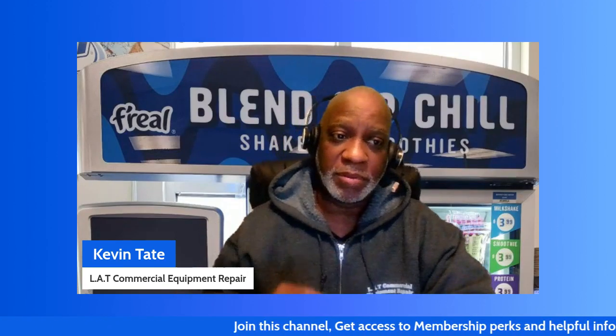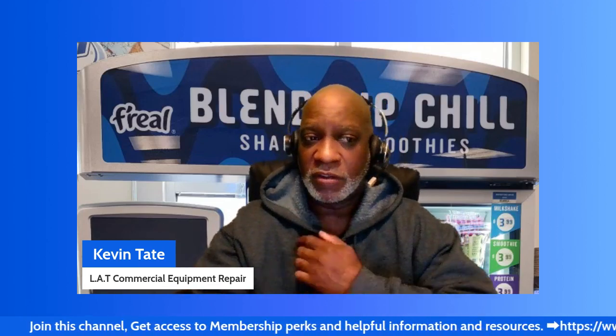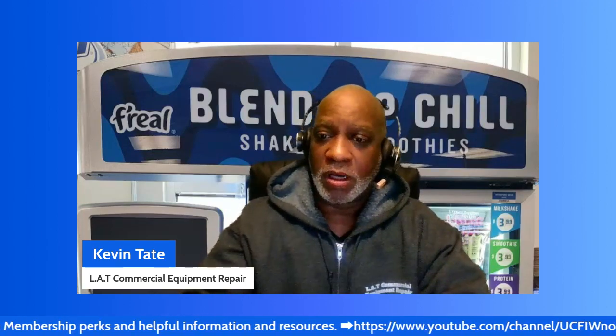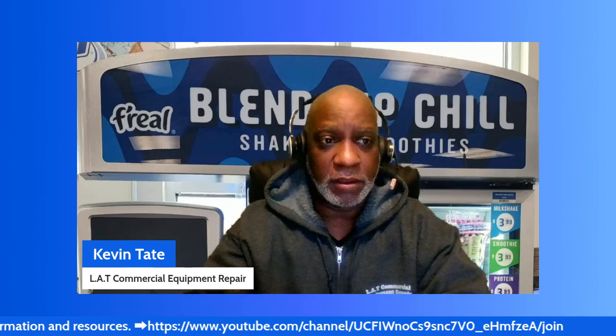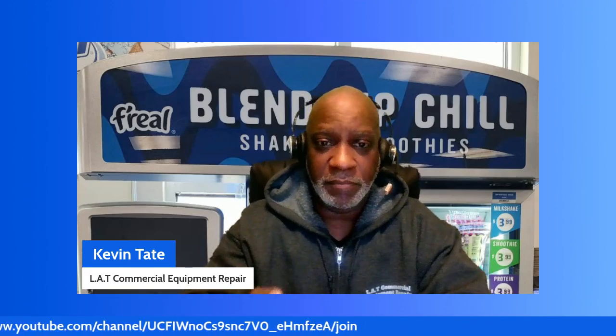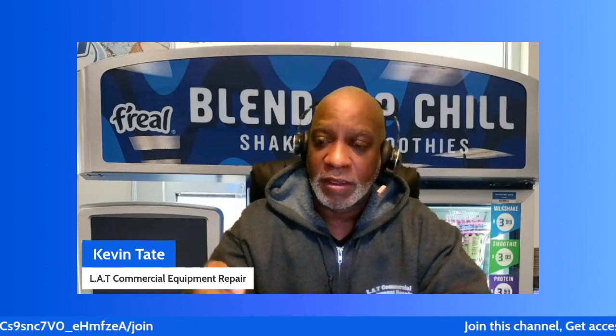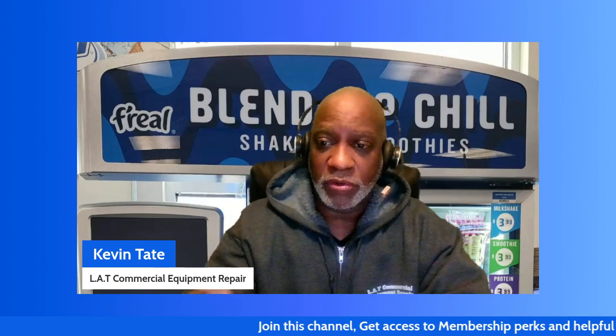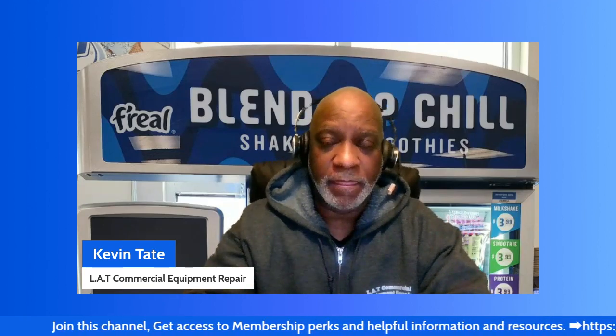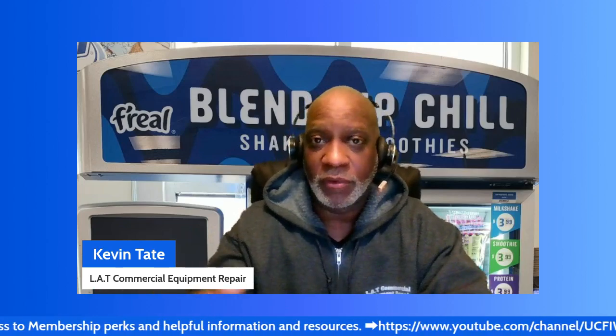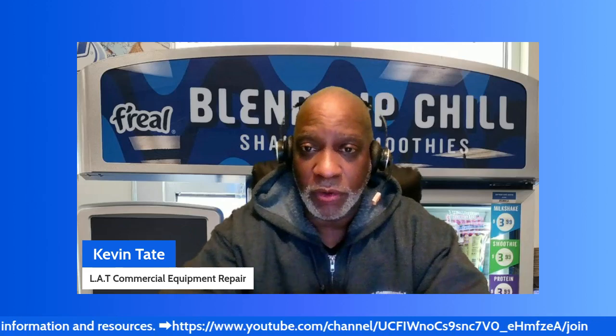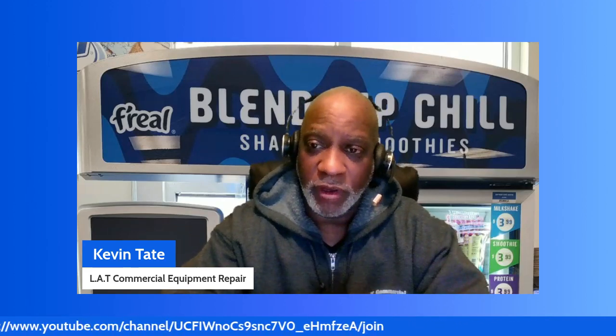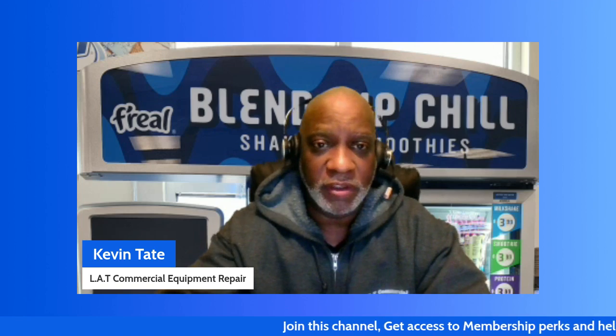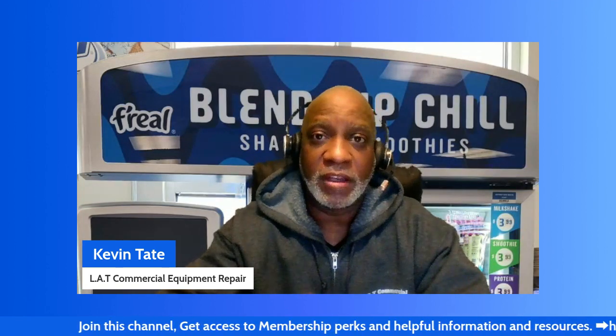You'll want to order that board and the motor and replace those at the same time. Don't take a guess and replace the HVCB board first, then test it, because if you don't replace the motor and the board together, more than likely that motor's going to blow that board again. Then either you or the customer will have to order a new board and a new motor all over again, so you want to avoid that. The best thing to do is order the mix motor and the HVCB board, then replace them both at the same time.